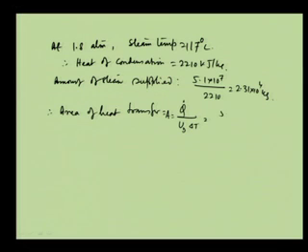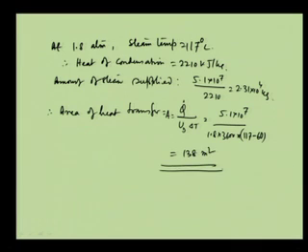So, U d is given. So, it becomes 5.1 into 10 to the power 7, that is the heat transfer by the steam, divided by 1.8 into 3600, per unit hour. 1800 is the joule, so this is watt per meter per second. It is per hour and kilojoule is maintained, so it is the unit conversion, into 117 minus 60. So, this gives 138 meter square. So, this becomes the area of the heat exchanger that is needed. This is just to give an idea about the evaporator heat transfer calculations.